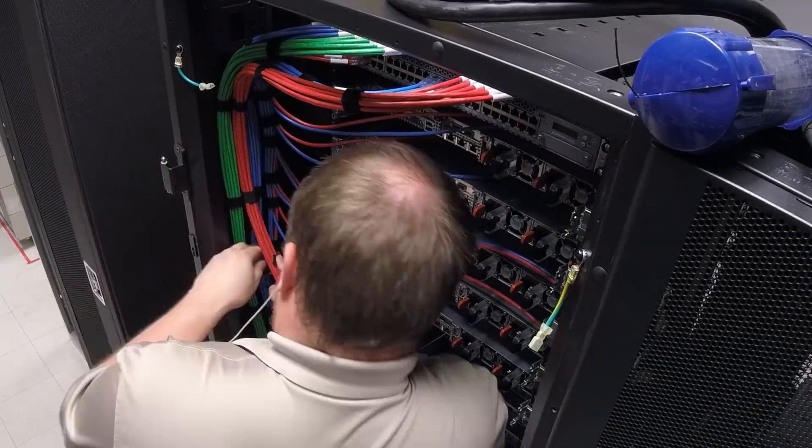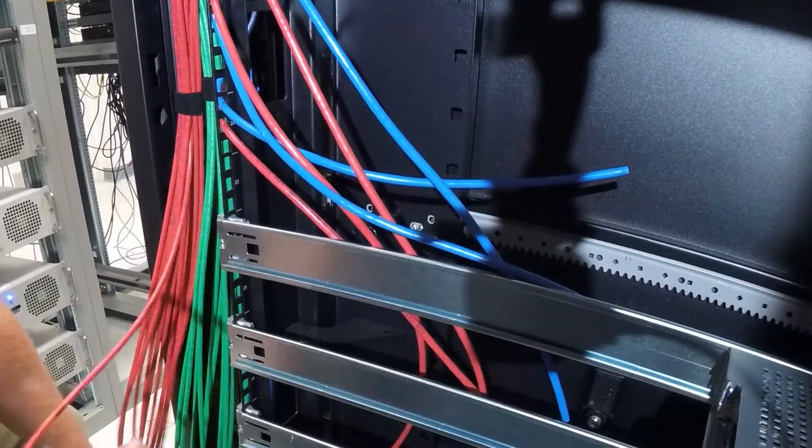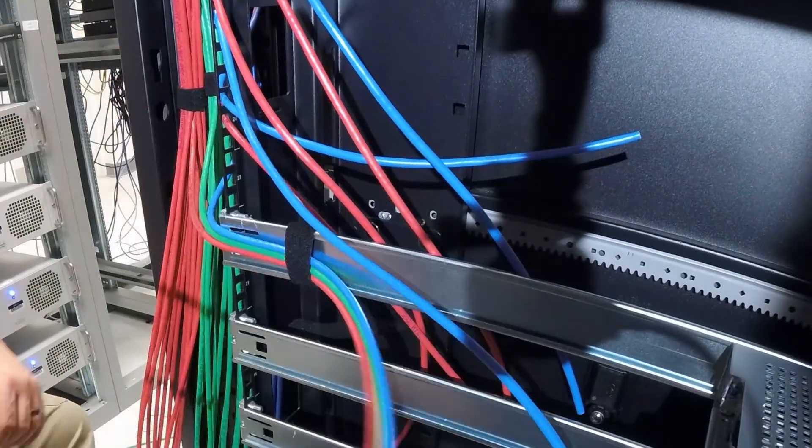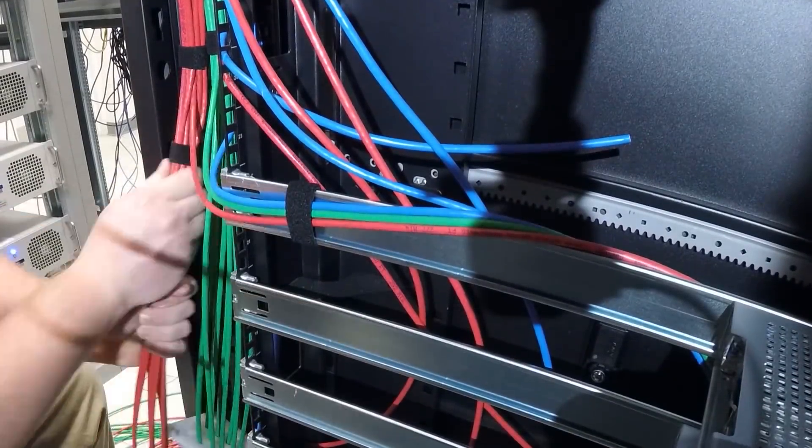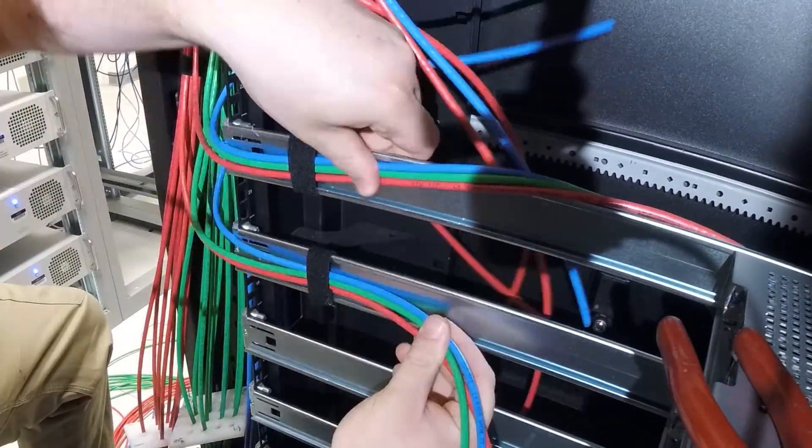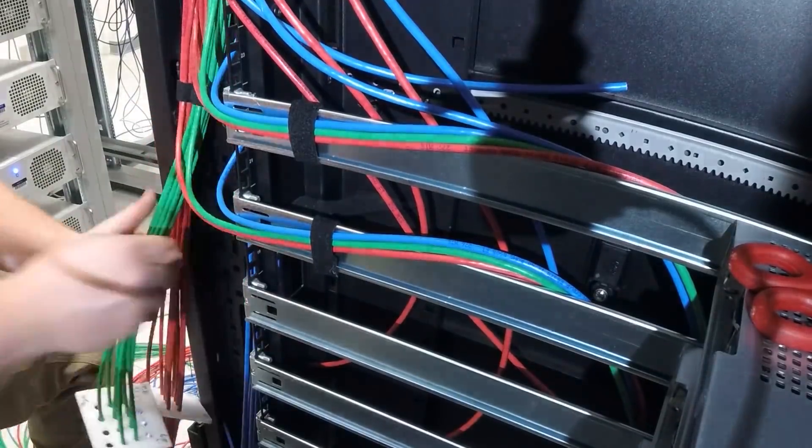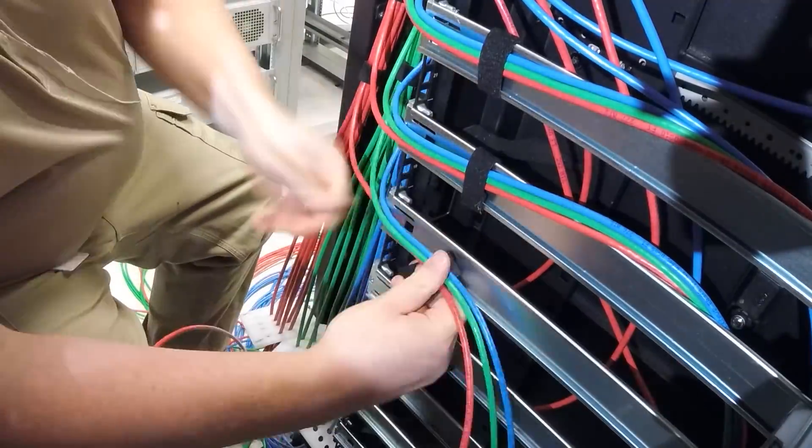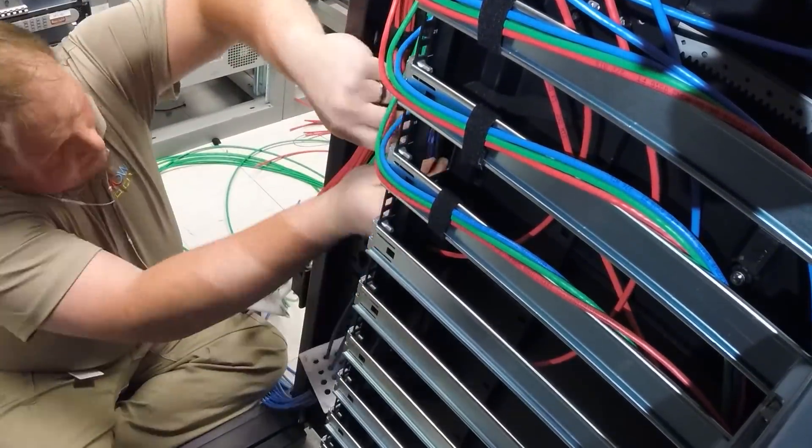I can't say enough good things about using hook and loop tape and a cable comb. These are the two biggest secrets that make it so much neater to run cables. We still use wax string for runs that are on our ladder racks, but for vertical stuff like this, hook and loop tape works great.